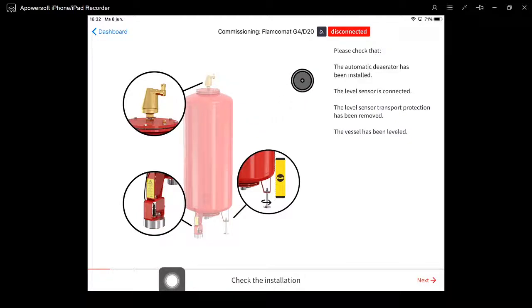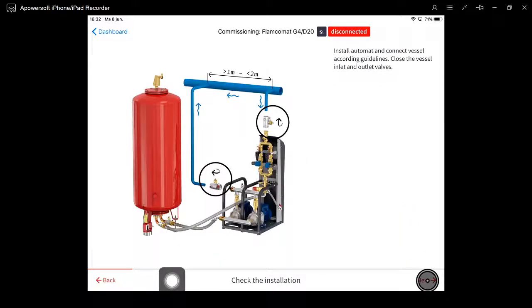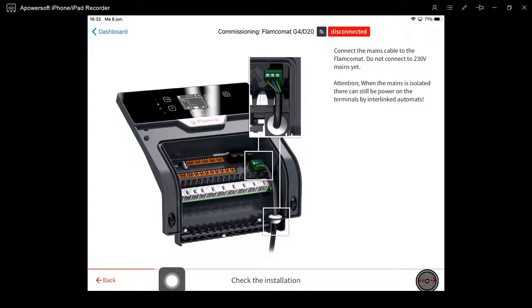First part of the commissioning is to check the installation, so checking all the points. When done, we can press next. Installing the automat and connecting the vessel according to all the guidelines. When we've done that, we can press next. Then we can connect the mains cable to the controller, but we do not connect the 230 volts to the mains yet.